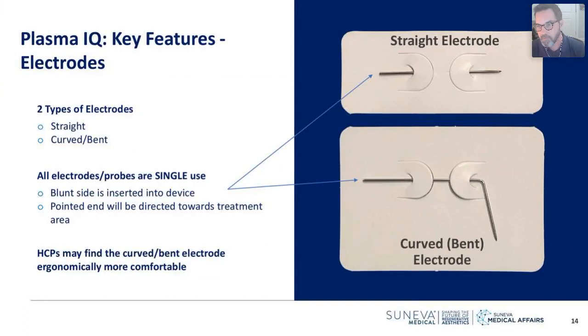So as I said, there are two types of electrodes, what we call the straight electrode or the curved or bent electrode. Most individuals, in fact, I would say probably 90% of the treatments that are being done today are with the curved electrode because it allows you to hold the device in a specific way that is more ergonomically pleasing, meaning your hand is not going to get tired nearly as quickly, and you're going to be much more precise in your energy delivery with the curved or bent electrodes than the straight. That's not to say that some people don't prefer the straight over the curved electrode. I would say make your own assessments and judgments about how you want to hold the device and deliver the energy, and then that will become your electrode of choice.